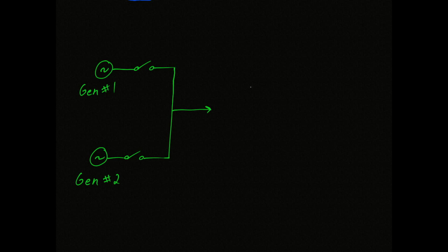To understand this cyber attack, we need to talk about generators and synchronization. On that particular day, we had 2 generators online. Each generator has its own circuit breaker. On this side, the circuit breakers are connected together and the resulting power heads off to town. You'll notice I'm using a one-line diagram here, where each wire represents 3 wires for our 3-phase system.